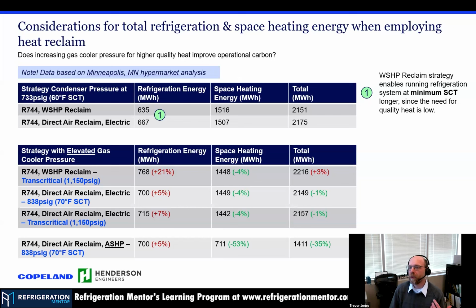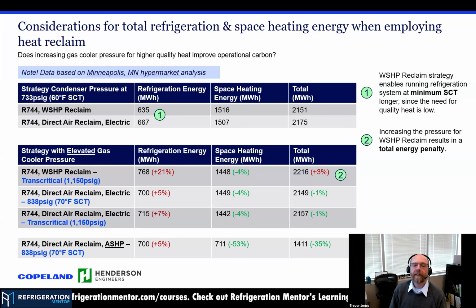So we looked at it both for the water source heat pump and the direct reclaim, whether or not it made sense to push your head pressures higher. And looking at the water source heat pump, there's actually a little energy penalty. It actually costs you more. You do get more heat, but you're spending more power to get that heat. Yeah, makes sense.